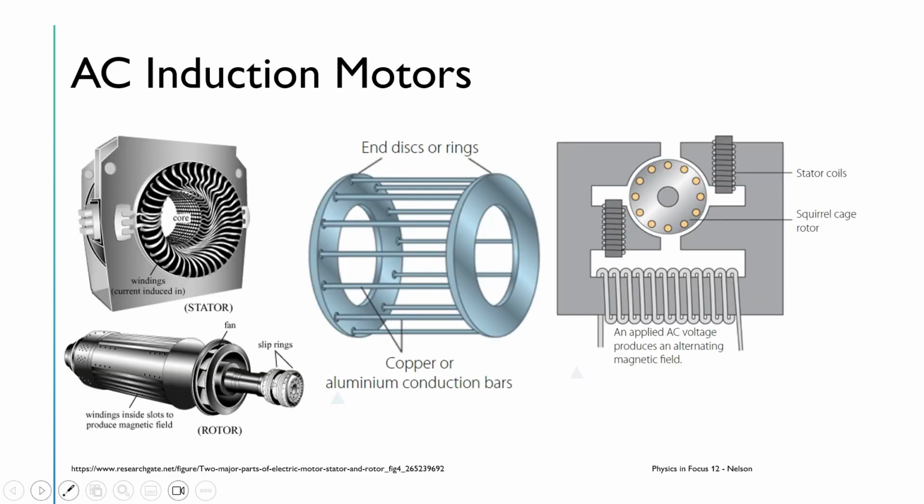So first off, an AC induction motor comes with two very clear and key sections. We have the stator, which is supplying a magnetic field to the rotor, which is the section of the motor which is actually rotating. The stator inherently is stationary. Generally in the rotor, you have what we call a squirrel cage, which is a cylinder with very defined separate sections of conductive material. This material can experience induced current from magnetic fields which are generated by the stator.